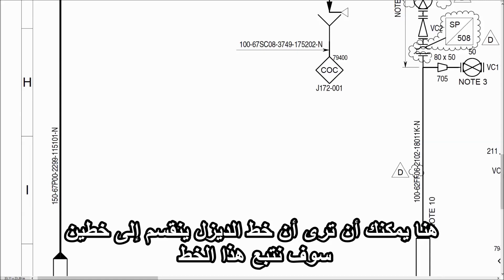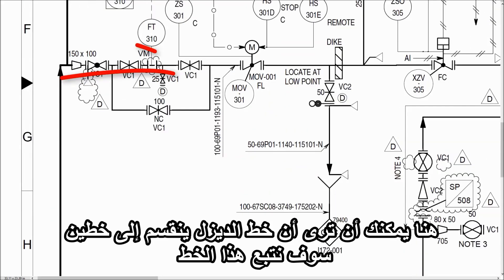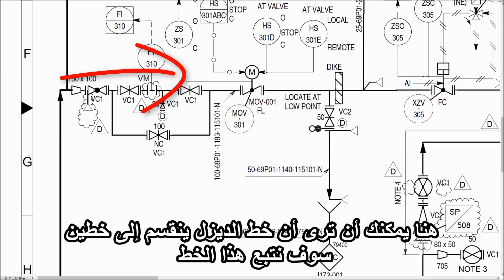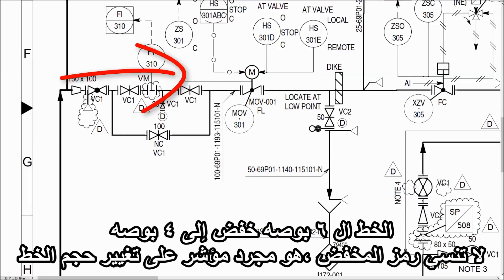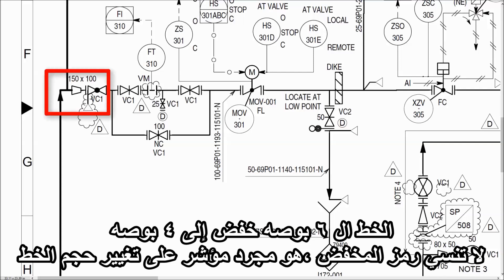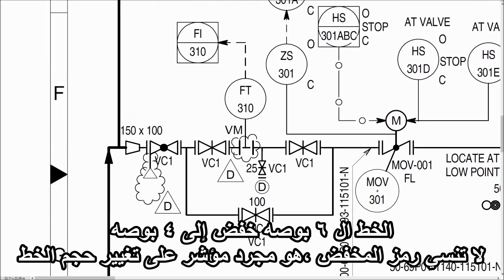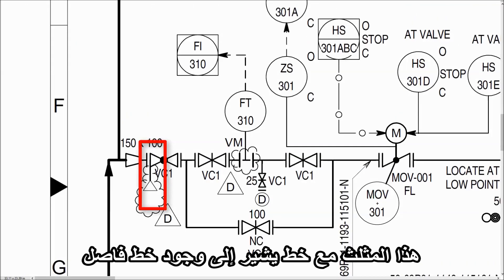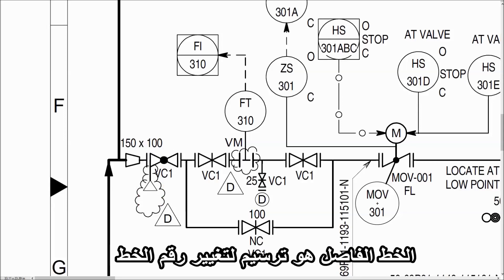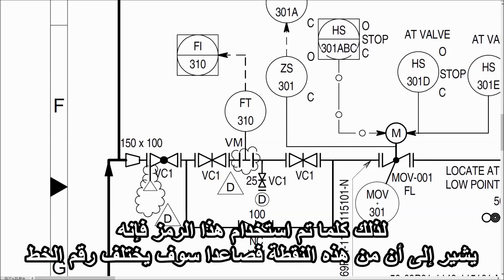Here you can see that the diesel line is divided into two streams. We follow this stream. The 6 inch line is getting reduced to 4 inch. Don't get confused with the reducer symbol — it is just an indication of the line size change. Now, this triangle with the line indicates a line break, which is the demarcation of a line number change. So whenever this symbol is used, it indicates that from that point onward the line number is different.